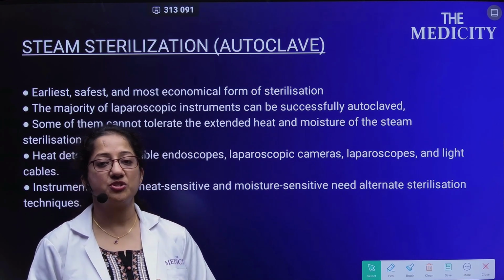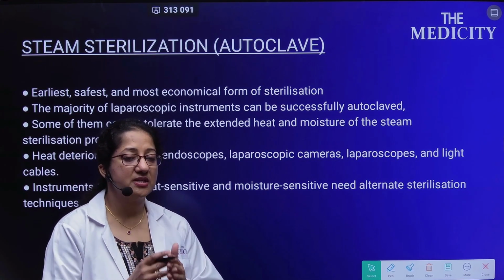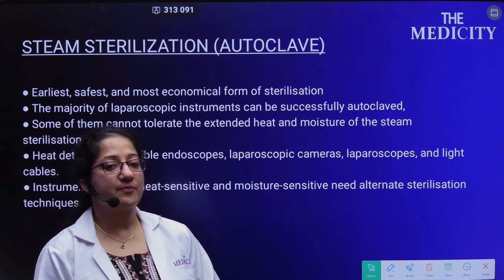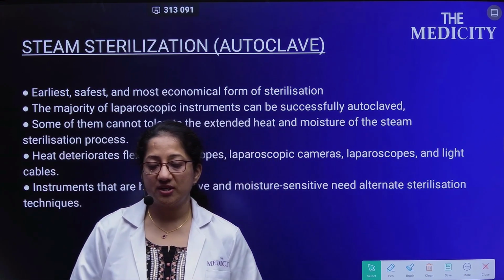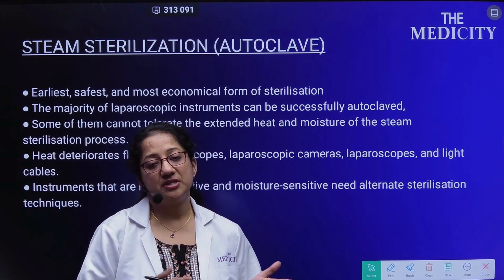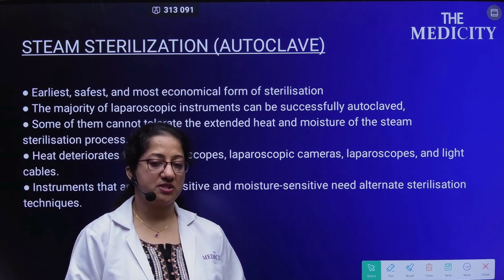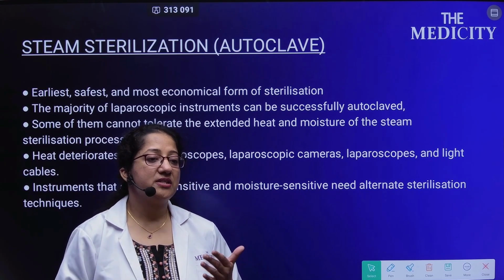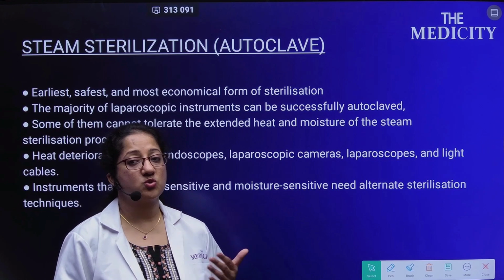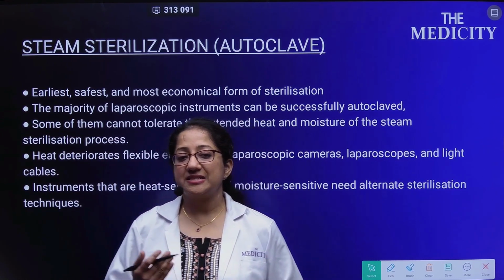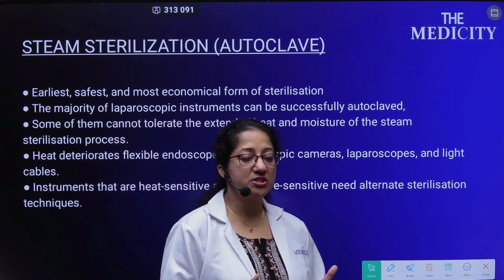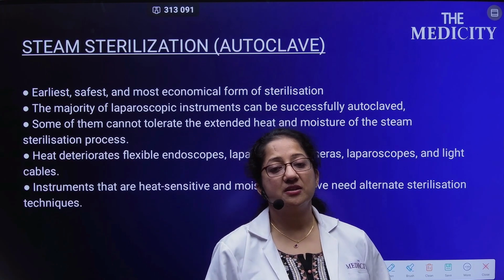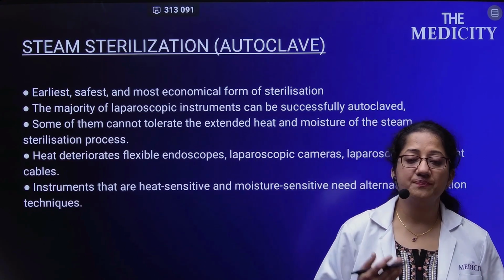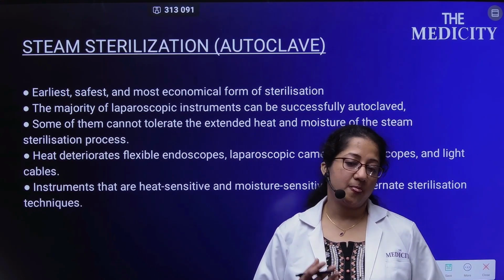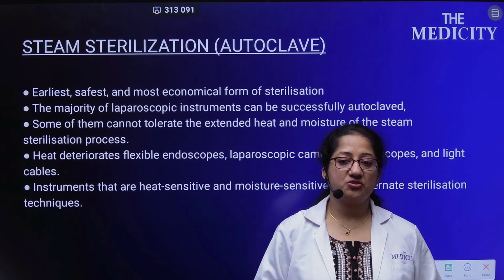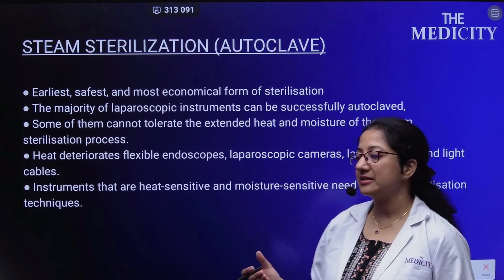The earliest, safest and most economical form of sterilization is steam sterilization. The majority of the laparoscopic instruments can be successfully autoclaved, and some of them cannot tolerate it; those we should know, otherwise we will spoil those expensive instruments. Heat deteriorates the flexible endoscopes, laparoscopic cameras, the laparoscopic lights and cables. So those things should not be put in the heat autoclaves. Those basically are sterilized using the sanitizers which we use in the hospital. Instruments that are heat sensitive and moisture sensitive need alternate sterilization techniques.